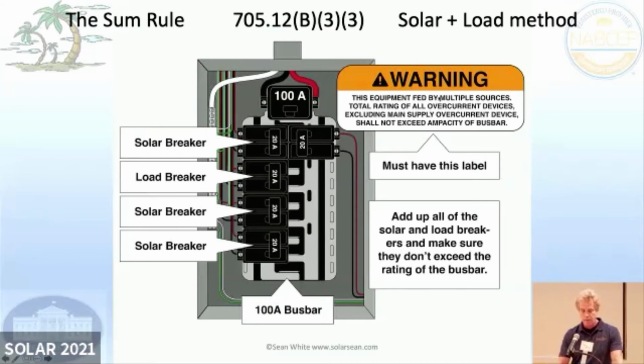This equipment fed by multiple sources, total rating of all overcurrent protection devices, excluding the main supply overcurrent device, shall not exceed the ampacity of the bus bar. You ignore the breaker protecting the bus bar, and we're just protecting this bus bar in reverse, and we're kind of overcompensating. And so you just add up all the breakers, solar and loads, you put them wherever you want, and they just can't exceed the rating of the bus bar. And this is actually being used kind of a lot. We're going to even look at what they call the Hawaiian tie-in.